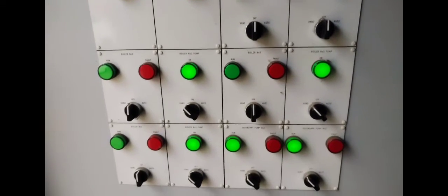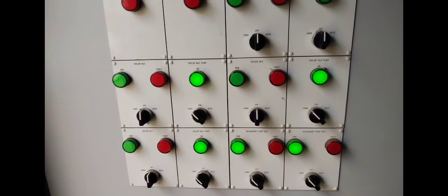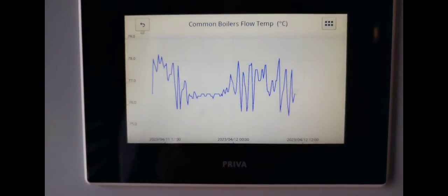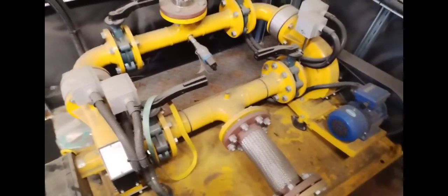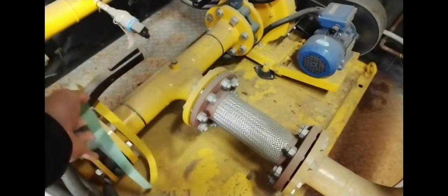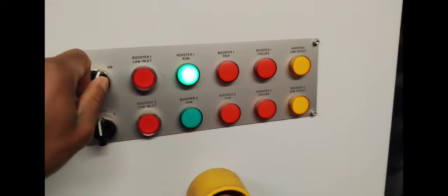Here I am turning off the power to the boilers, aiming to leave the pumps on so that it can circulate the heat so that there's no kettling that takes place. These are the temperatures that we have the system on, and this is the diagram showing the pipework. This is the gas booster set — we've got two gas boosters — and I'm going to turn the gas boosters off.